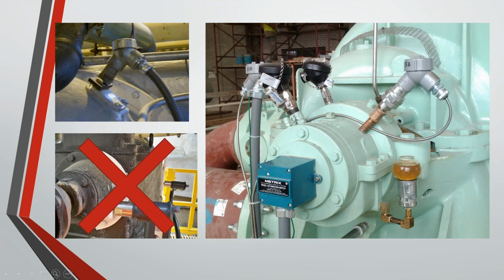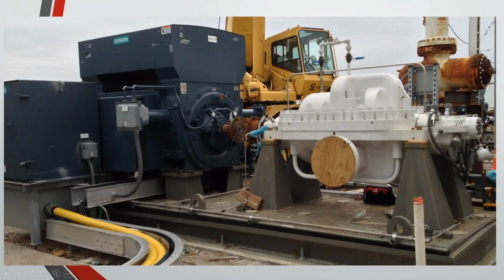And then over here, I just wanted to show you a machine with a switch on it. This is a switch mounted to measure axially. And then we've got some vibration probes installed in the X and Y orientations. You can't see the one behind the temperature sensor, but you can sort of see it over here. You've got orthogonally mounted vibration probes looking inside the machine. And real quick, I'm just going to show you what that looks like inside the machine. So here's a different machine. This is a pump, and over here on the far right, you can see we've got some proximity probes, again mounted orthogonally in the bearing housing.